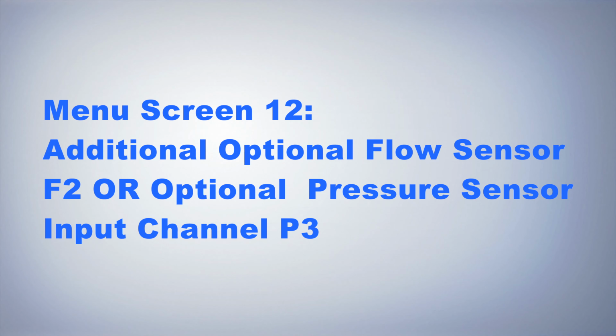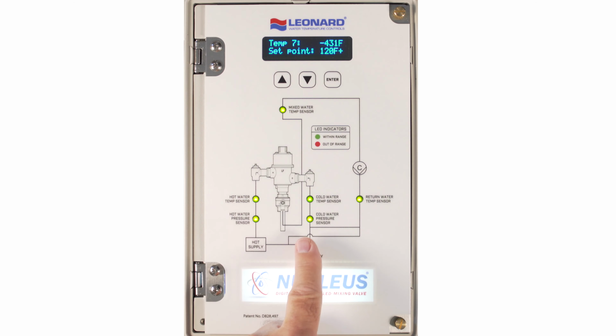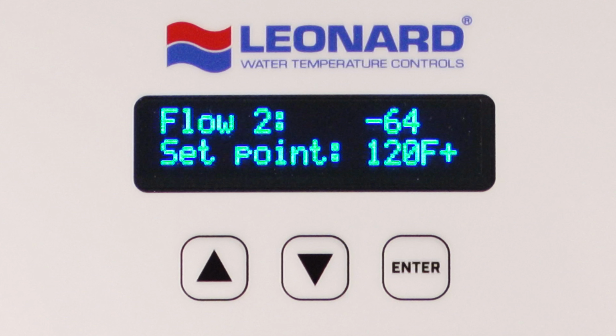Menu screen 12. Additional optional flow sensor, F2, or optional pressure sensor input channel, P3. Pressing down 12 times displays flow 2 or PSI 3. This indicates and displays actual flow in GPM on flow channel 2 for the optional daughter board. If this input was commissioned as a third pressure sensor, the screen will display the pressure P3. See O&M manual for wiring setup. Note: a large negative value displayed at the flow 2 or PSI 3 line is an indication that there is no sensor installed to the main control board, or the wiring to the main board is improper, or the sensor is damaged.